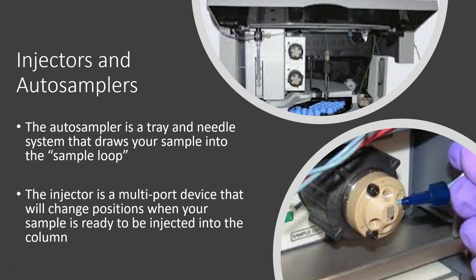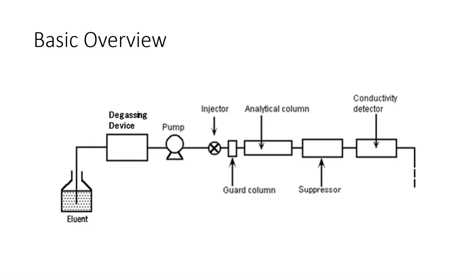The injector is a multi-port device that will change positions when your sample is ready to be injected into the column. Normally this injector is in a position where eluent can flow through it and straight into the column, but as soon as your sample is in the sample loop and ready to be injected, this port will open up for your sample to go into the column, inject the sample, and then it'll go right back to eluent so that eluent can continue flowing through the system.